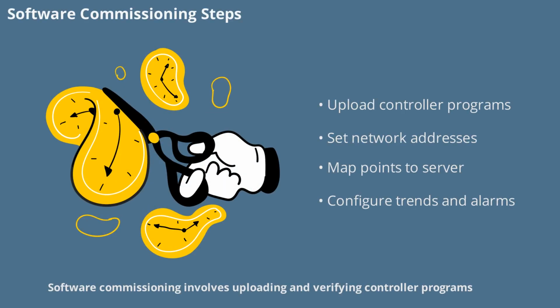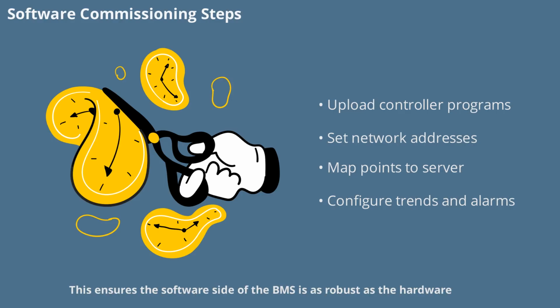Software commissioning involves uploading and verifying controller programs, setting network addresses, and mapping all points to the server. Trends, alarms, and schedules are configured, and logging or alert features are enabled as needed. Finally, all project data is backed up and saved. This ensures the software side of the BMS is as robust as the hardware.